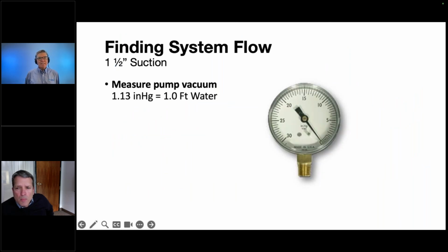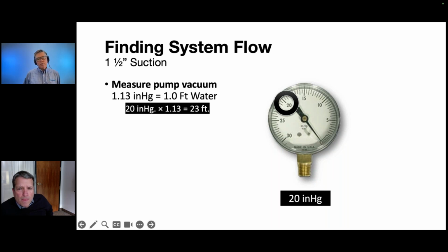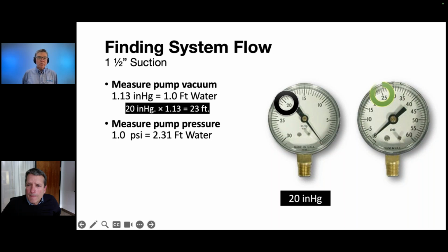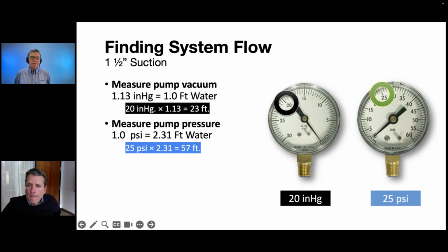So now if we take this exact same process, but now we're dealing with a 1.5-inch system, where the first one was a 2-inch system, you can see now with the same pump our TDH has gone way up. Our vacuum level has gone up from 10 to 20. This will be in cavitation or very close to it. Obviously, with small pipe, our pressure tends to go up also.